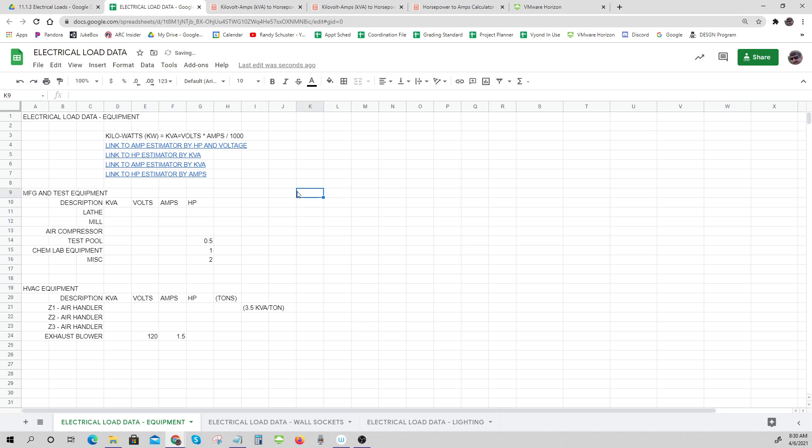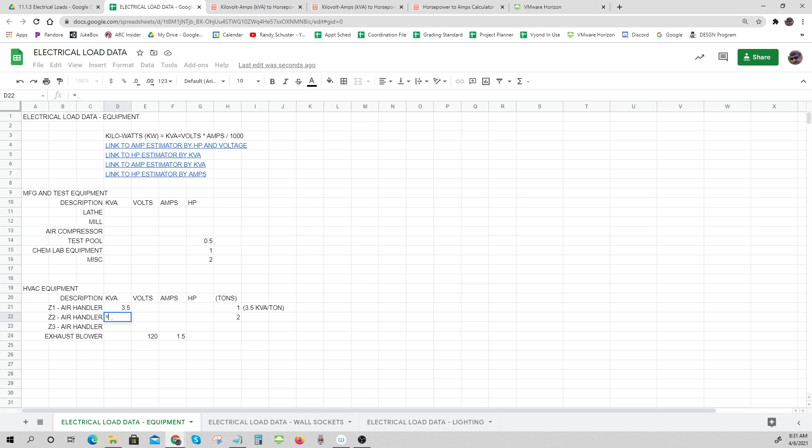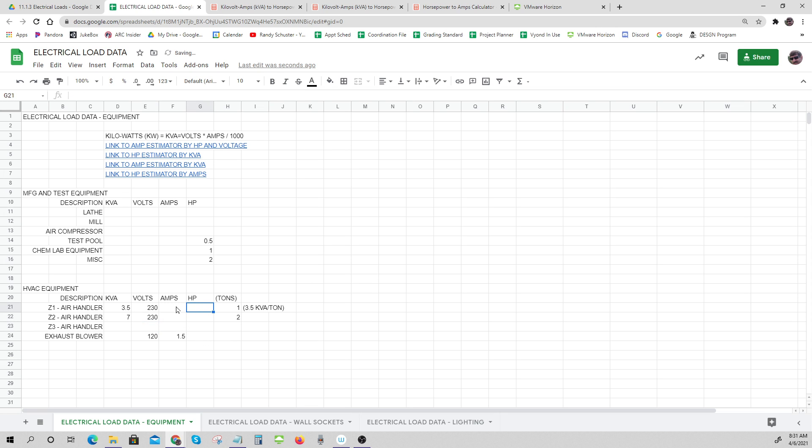Now when I get down to my air handler, it's a little bit different. You have already figured out how many tons your air handler is. So you'll write down, let's say in zone one I had a one ton air handler, and I've given you the equation: 3.5 kVA per ton. So that's one ton equals 3.5 kVA. If it were two tons, of course it would be twice that. So then I can start figuring out my kVA. Now normally you get to choose, but most air handlers run on 230 volts. So you can find your horsepower and your amps from that.